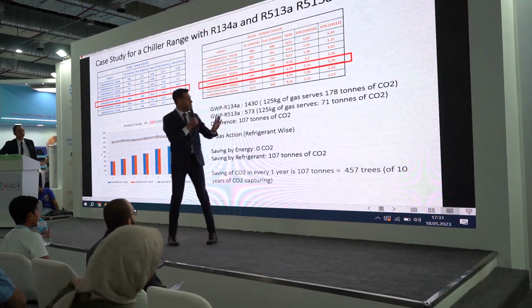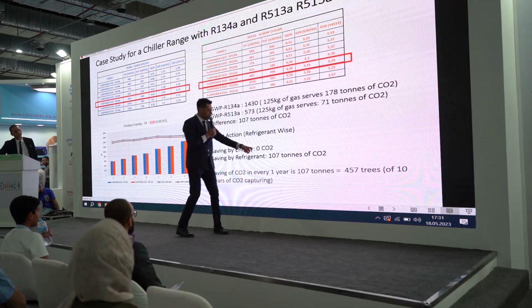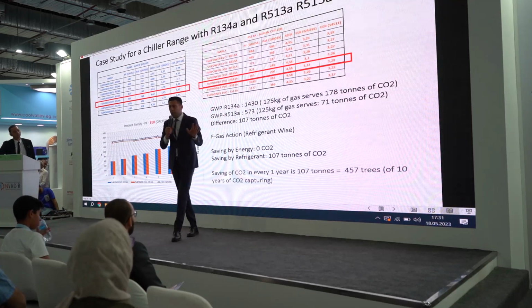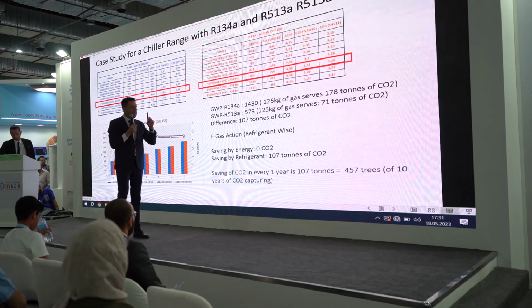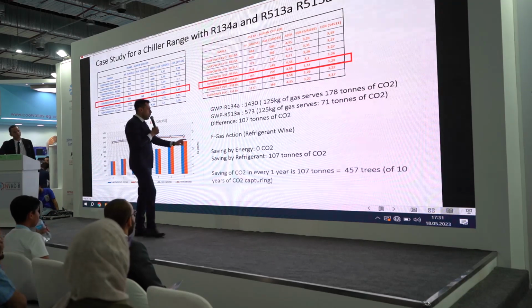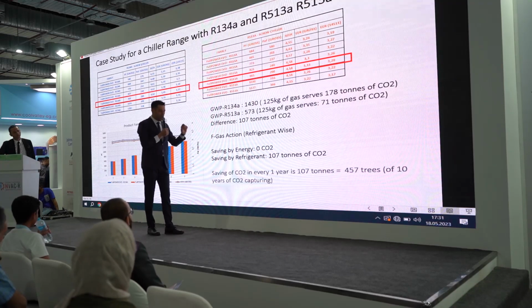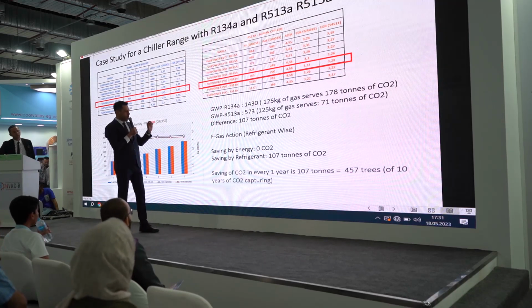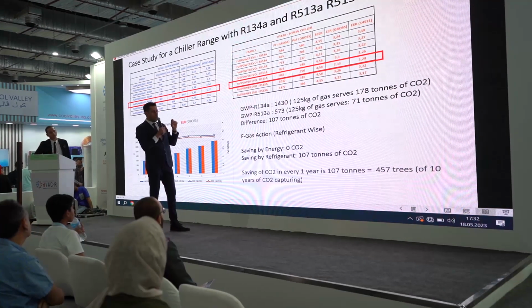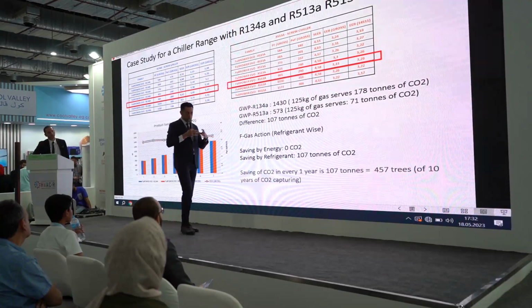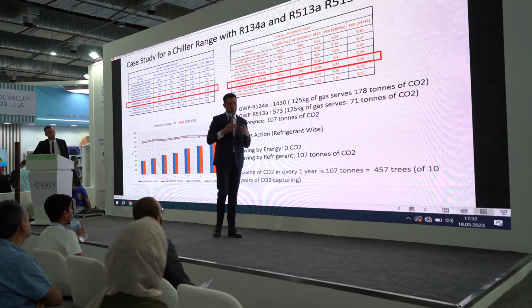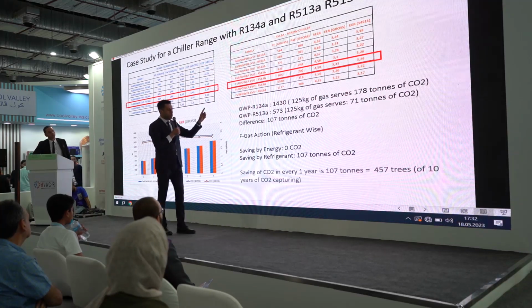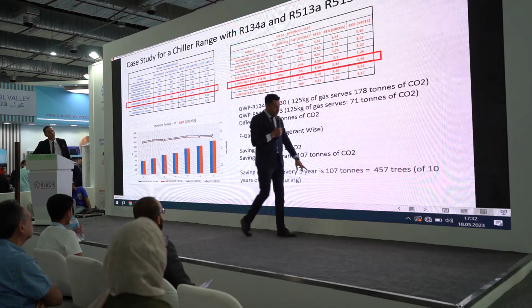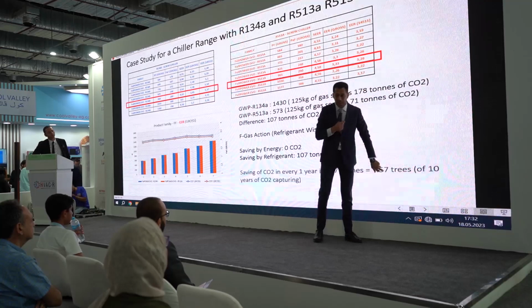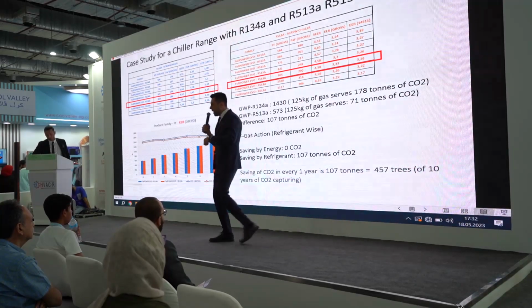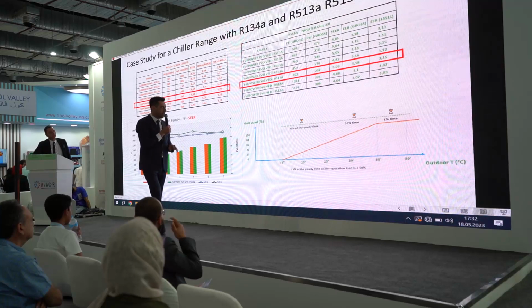The saving of the energy is zero, you see. No, because energy-wise they are the same unit. So I see the changes refrigerant-wise. So making the necessary calculations, just changing the refrigerant, over 10 years of operation, one tree with some certain conditions, the trunk thickness 25, I'll be showing it to you. So just by changing the refrigerant, every year you are saving 457 trees. 10 years of operation, but every year you are saving 457.